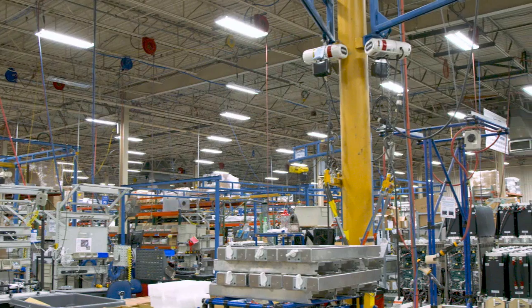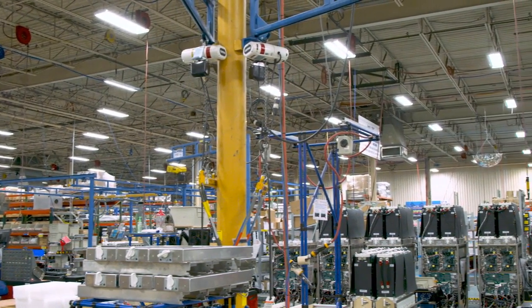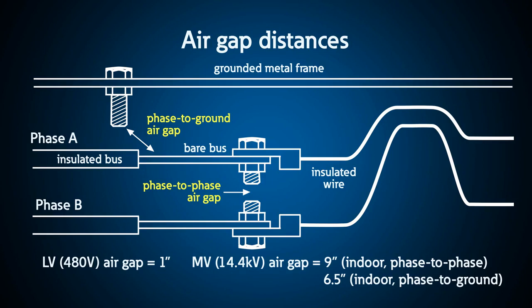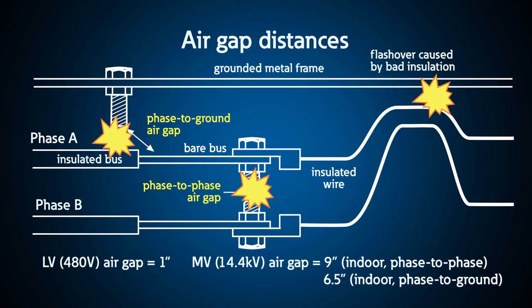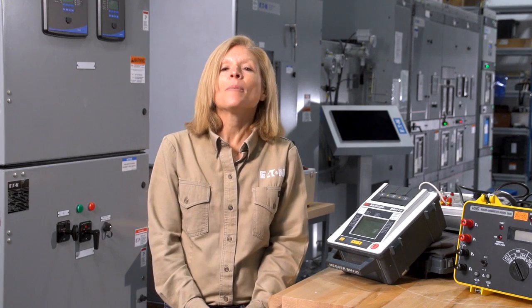The insulation of a piece of equipment is never as good as the day it leaves the factory floor. Insulation quality can get worse over time because of different environmental conditions like temperature, moisture, humidity, and dust or dirt. Along with proper insulation, ensuring appropriate distances or air gaps between current-carrying conductors and its metallic shielding is important. If the quality of insulation or space between phases or phase to ground are not tested and verified, it could result in system or equipment failure or danger to personnel. There are a couple common tests that can be done to verify these concepts.